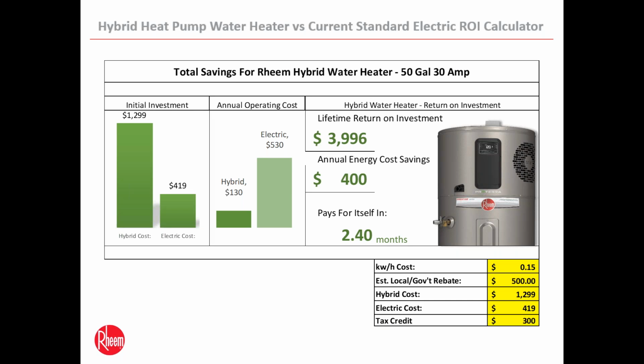Now, this is a real eye opener when it comes to what your return on investment is. This is comparing a 50 gallon, 30 amp hybrid heat pump water heater versus a standard tall 50 gallon electric. These are estimates and averages that I'm sharing with you, so this could deviate based on kilowatt hours and what is typically charged. You can expect on a 50 to pay somewhere between $1,200 to $1,300 without any incentives offered by utilities. But I encourage you to look to see what incentives may be out there from your local utilities. The initial investment for a standard electric water heater, which is relevant to your market, is around $400, $420.